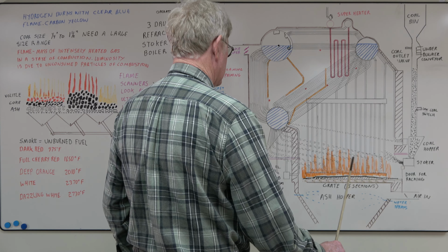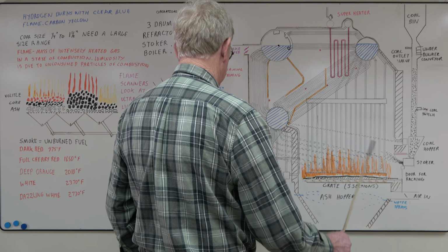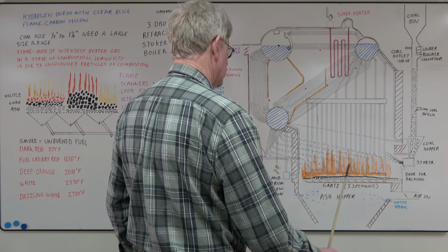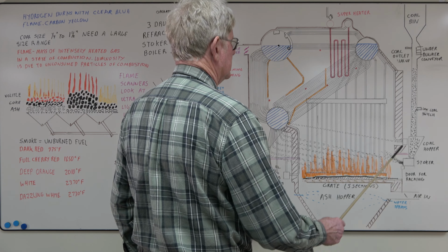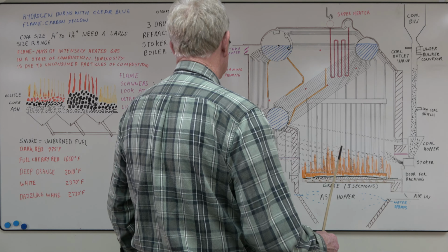They would track each other. There was a boiler master, and each boiler had its own controller that would pull this fuel rod back and forth to control the feeding rate on each stoker. And jamming stokers was the big problem, some debris coming through and sticking. And that's about it.